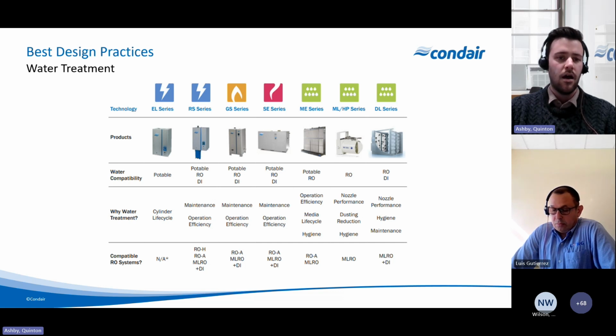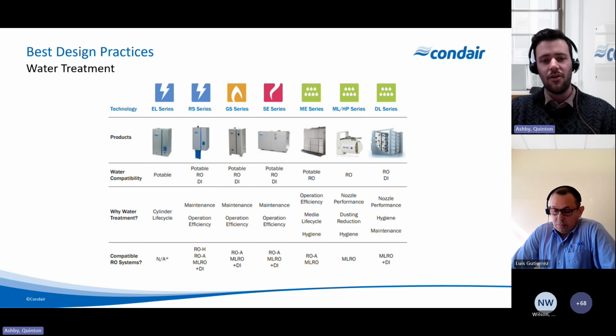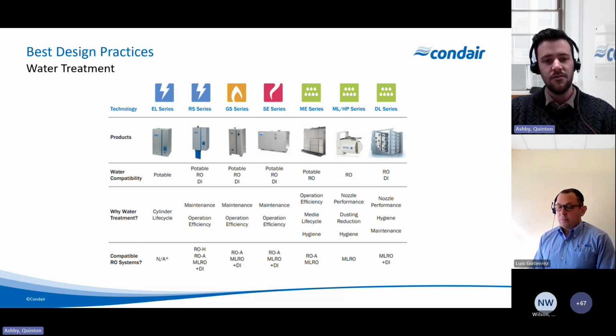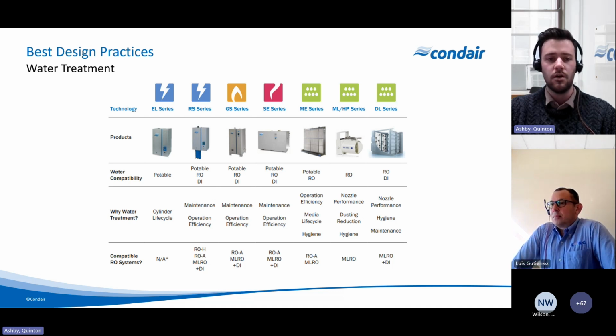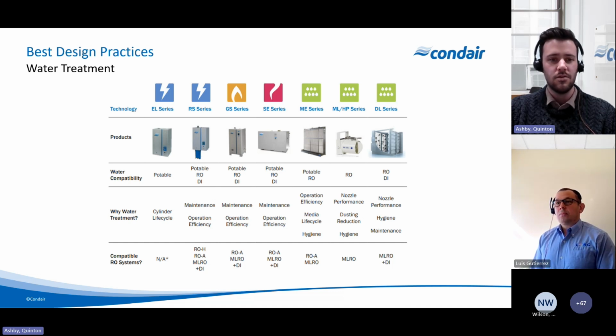That's all laid out. In terms of why we would use the water treatment systems, if we don't need to, for isothermal, there actually is no hygiene incentive. You're boiling the water, so there's no risk. Essentially, it's just for prolonged efficiency and maintenance requirements. So if you want to reduce maintenance, you can treat that water. A little bit different for adiabatic. So it does increase operational performance and reduces dusting. So that's the minerals in the space itself, and reduces maintenance. At the same time, since we are using cold water, we want to make sure that we're removing all bacteria. So we do have other hygiene components in there as well, but we want to make sure we're cleaning it well. And I'm running slow, so we'll get going.